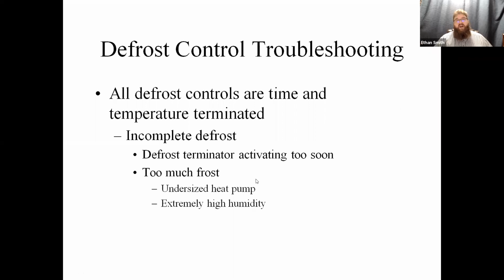Okay. High humidity environments. Case in point, we've got installations near bodies of water, and they build frost really rapidly. And so you may have to have a termination temperature that's a little higher to combat that excessive frost buildup. I in particular had one here in Utah where we typically don't have humidity problems. We live in a high altitude desert here.